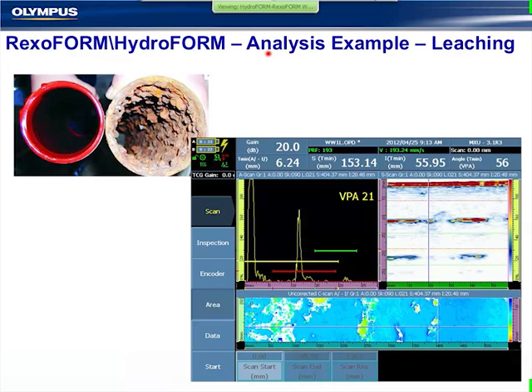I'm also receiving a lot of questions regarding the bubbles. Bubbles in the HydroFORM get in the way of the data. Having a water supply where all of the fixtures are tight and secure and it's not sucking air into the system dramatically improves this. Keeping the water supply immersed in the water and not allowing it to have bubbles inserted into it in the beginning also makes this much easier. And certainly the water supplies provided from Olympus take this into account. We see some of them out in the field from third parties where that was never a concern, and it's causing a lot of problems.